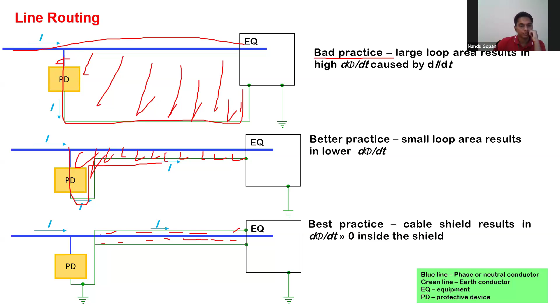Next, I'll give some examples of what I've explained so far. The first example is a good SPM - surge protective measure. So you have a building, and this is the outside air, which is LPZ 0, while the building is LPZ 1. Suppose in this building area I've used RCC steel and made a good shield, and also used an external lightning protection system - this is the shield. Next, I have room 1, and there also I've put some shielding - shield LPZ2. And I have equipment 3 in room 1.